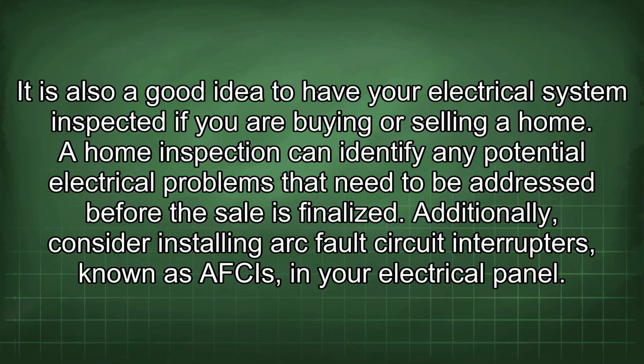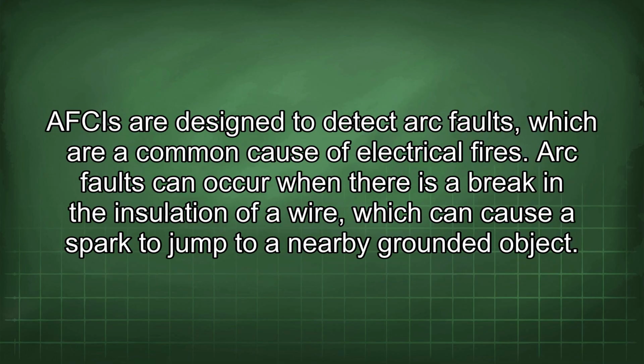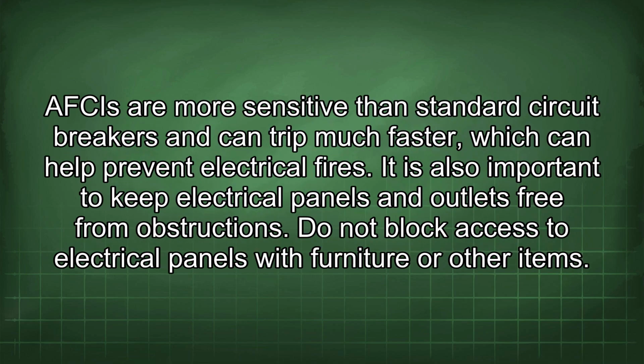Additionally, consider installing arc fault circuit interrupters, known as AFCIs, in your electrical panel. AFCIs are designed to detect arc faults, which are a common cause of electrical fires. Arc faults can occur when there is a break in the insulation of a wire, which can cause a spark to jump to a nearby grounded object. AFCIs are more sensitive than standard circuit breakers and can trip much faster, which can help prevent electrical fires.